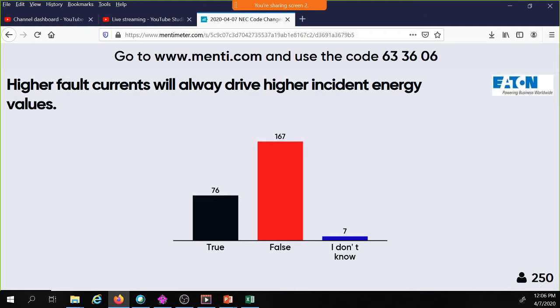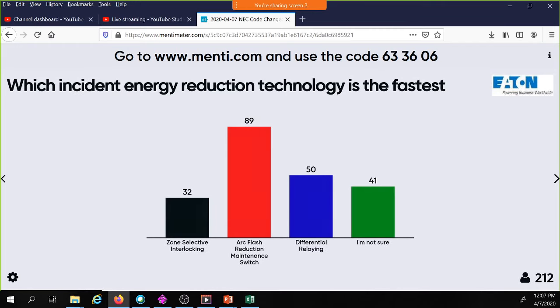So I've heard people say, all I need to do is lower the fault current, and I'm going to lower my incident energy. And when they did the calculation, they realized the actual energy went up, and they couldn't understand that. And we're going to learn and understand that today together. So for those 76 here and the 7 on the phone, you're going to understand how important it is to understand fault current and the clearing time of the overcurrent protective device that's feeding power to that distribution equipment.